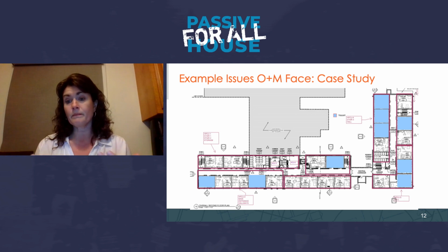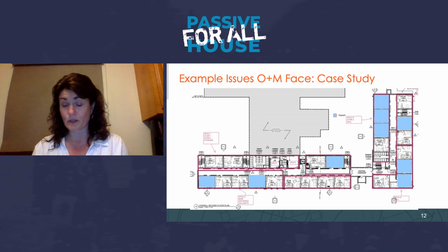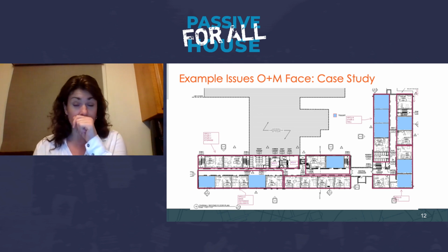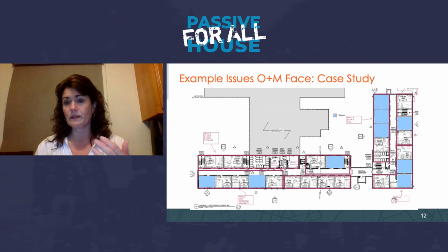But what the O&M staff was doing - the building supervisor - he was going around and, if the south side was overheating, turning their condenser back to cooling in the swing seasons, as opposed to the rest of the building. That's just a really intensive schedule for an individual to keep on a daily, weekly basis. These temperature swings in the swing seasons can go from 40 degrees to 80 degrees in September. So for someone to be responsible for switching that equipment over from heating to cooling on a daily basis, that's just not sustainable.